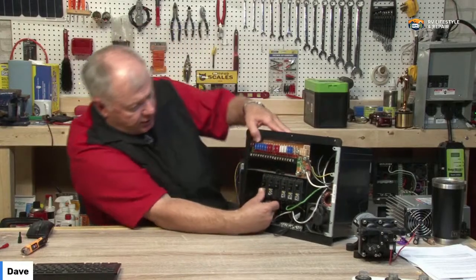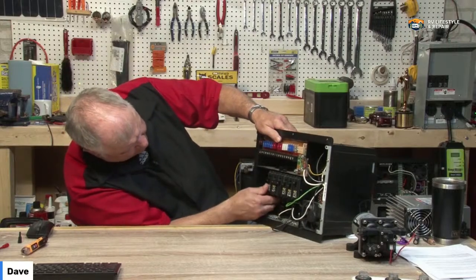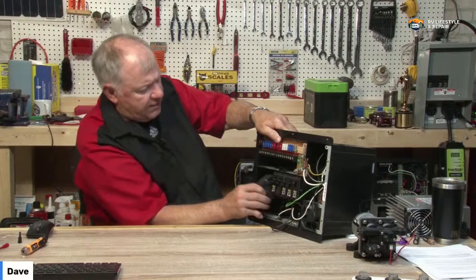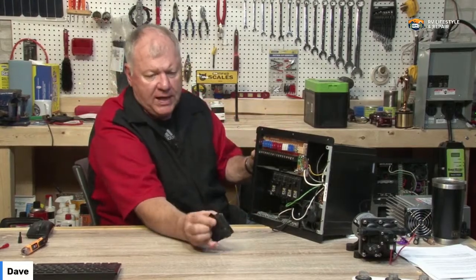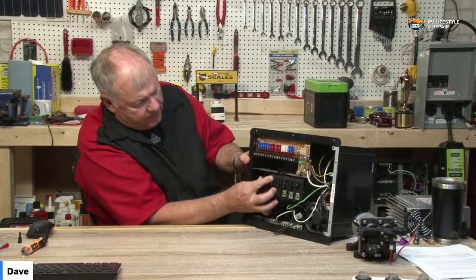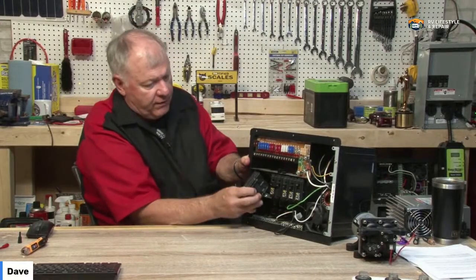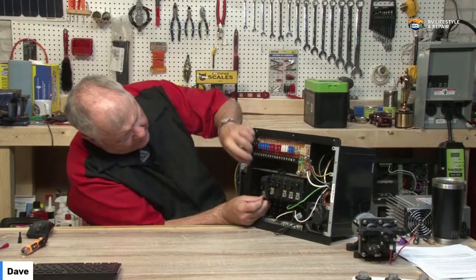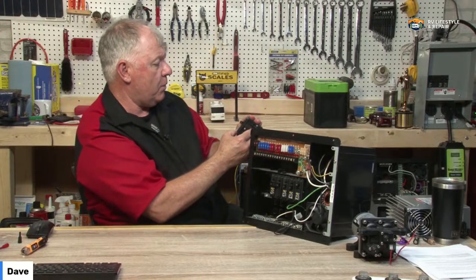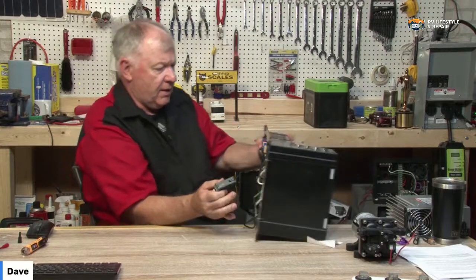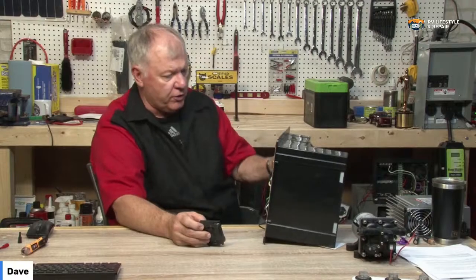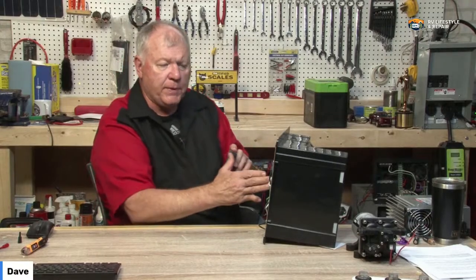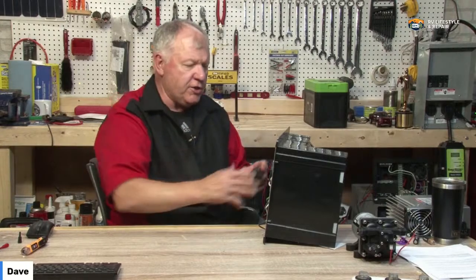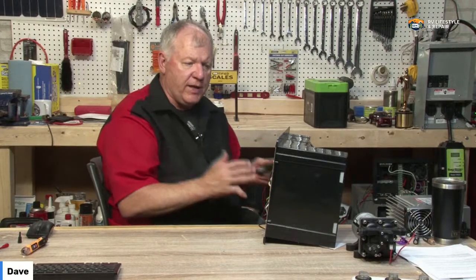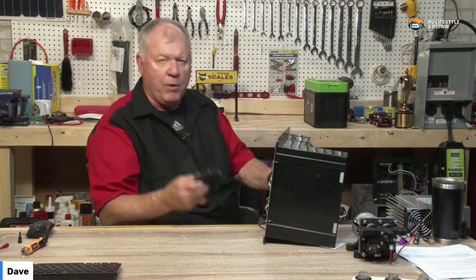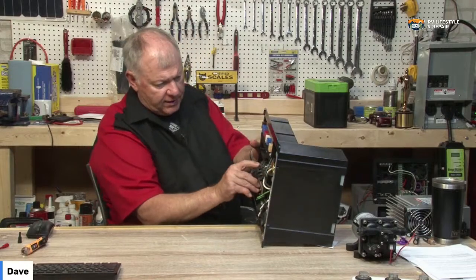Then you're basically just going to rewire these, since they're typically just residential style breakers that get put in. This is 120 volt, and it's a 20 amp, you can see there, same as you'd have in yours. You'd have the same breakers like this, but this half does the front air conditioner, and this half does other stuff with the back air conditioner. That way you split the two out, so you don't have both air conditioners on one leg.